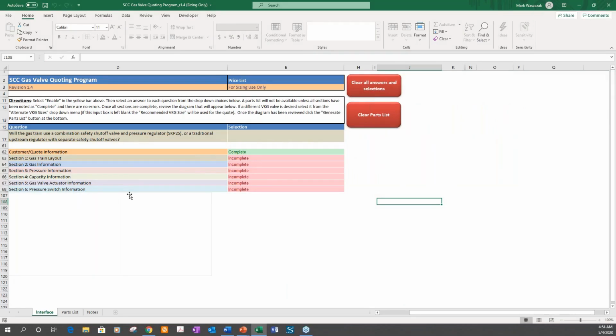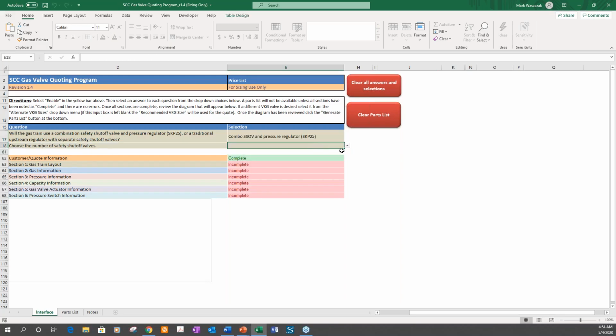Now, the sizing program allows you to select options based on your application. It includes drop-down menus and allows you to select the available options. Once this section is completed, it will proceed to the next section, ensuring that all the information has been provided. So we'll go through an example. First thing it asks is which gas train, or will the gas train use a combination safety shutoff valve and pressure regulator? And we will select the combo SSOV with SKP25.